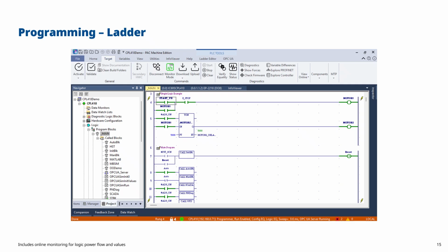My emergency stop is passing power. Normally you'd wire the emergency stop in the reverse state, so that's why it's a normally open, not a normally closed. And that means I'm allowing my motor contact on the right-hand side to be energized. Then I'm also using another motor contact on my main rung there to feed back and hold in that contact. So even if I removed my start push button, it would still hold itself in as long as the emergency stop push button isn't operated.